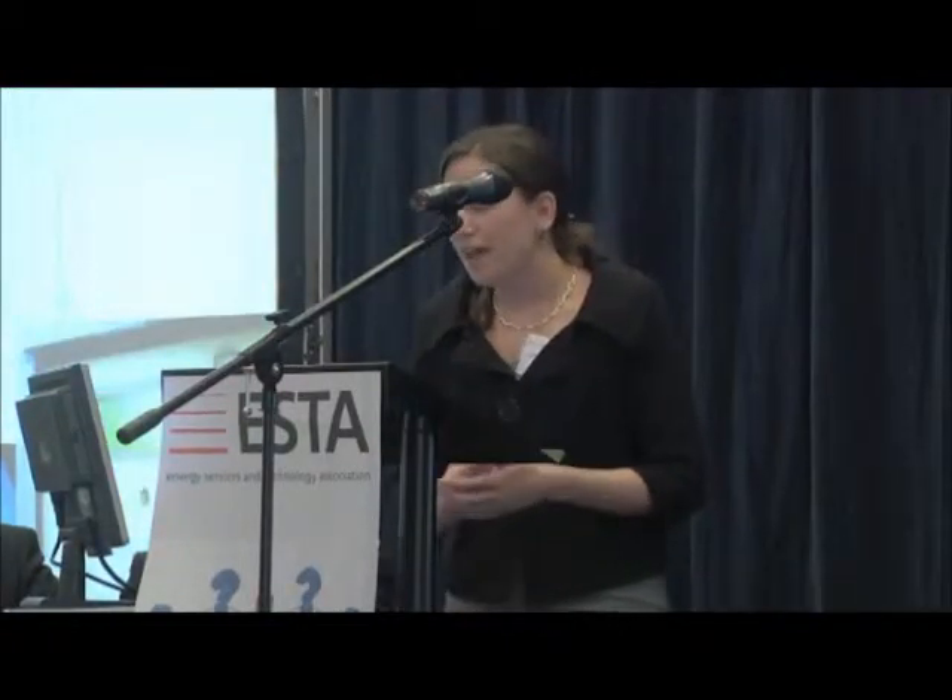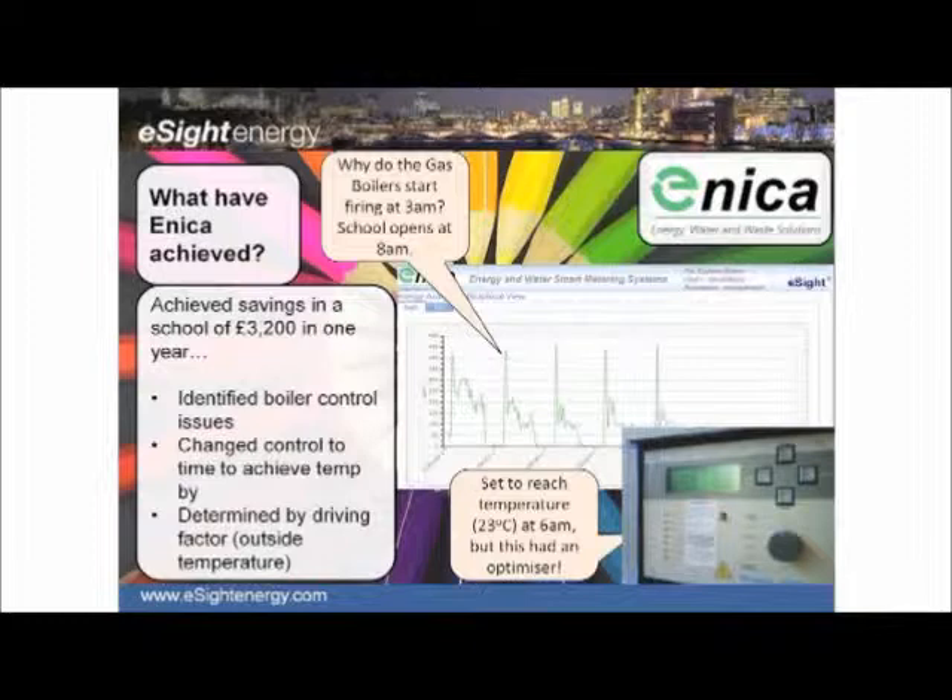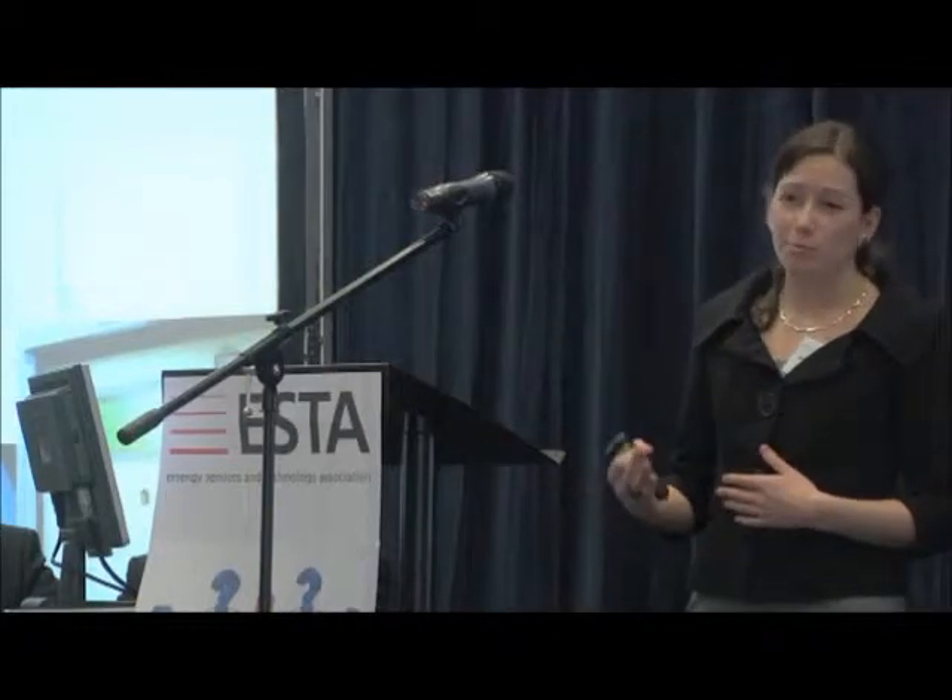Another example from Enica comes from a school, where they looked at gas consumption on a daily basis and quickly highlighted a boiler control issue. The school was set to open at 8 o'clock, but the facilities manager had set the boiler to reach temperature by 6am — two hours early — and had set it to 23 degrees. Enica found that boilers were firing at 3am to achieve that. They utilised the optimiser already available on the boiler to fire it at the right time based on external temperature, so it reached the correct temperature at exactly 8 o'clock — no sooner, no later, adjusting for warmer or colder days. By making no investment at all, they achieved savings of over £3,000 — simply by getting the school to utilise the technology they already had.